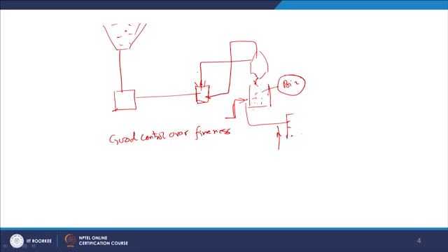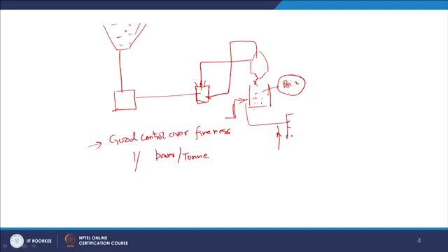In the unit system, the pulverizer has to be placed next to the boiler. So, the aisle side of the boiler will be obstructed by the unitary system. This is a central system. In the central system, the aisle side of the boiler is not obstructed. That is one of the major advantages. Power consumption per ton of coal is less in the central type of system. And the operation of the burner, because the pulverized coal is supplied from the bin, is independent of the operation on the other side. So, these are the advantages of this system.